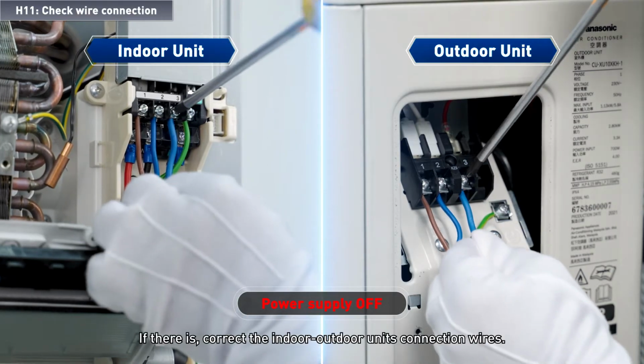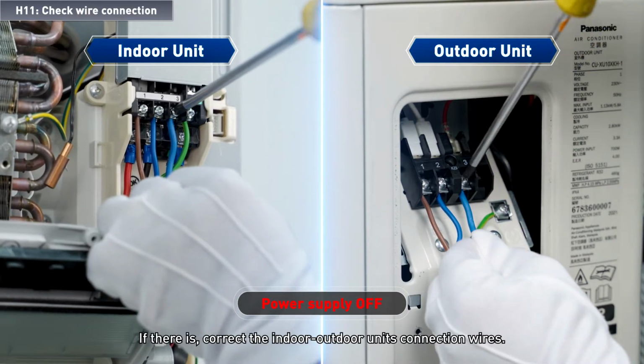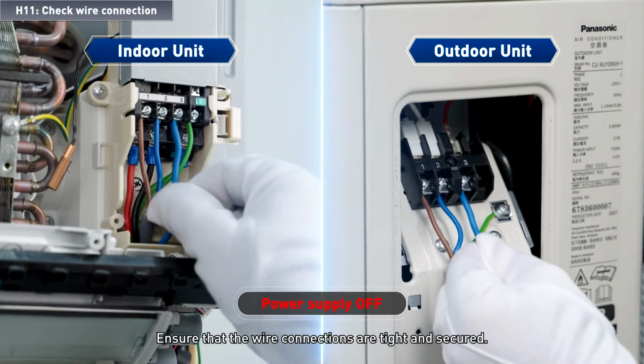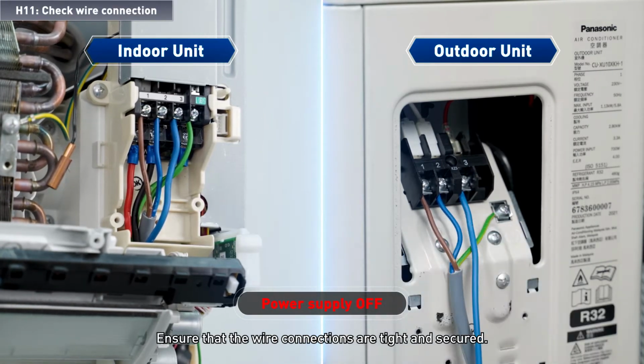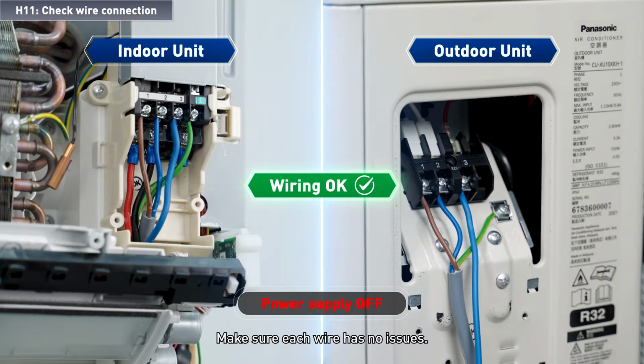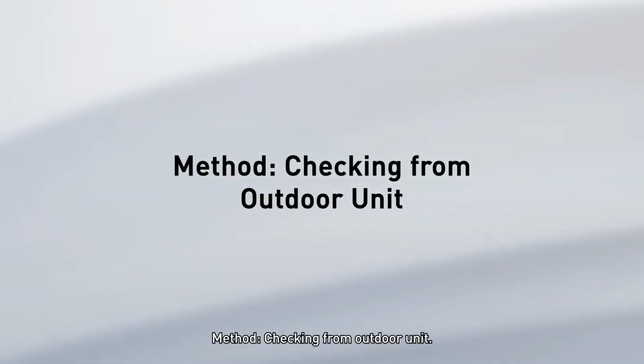If there is, correct the indoor-outdoor unit's connection wires. Ensure that the wire connections are tight and secured. Make sure each wire has no issues. Method: checking from outdoor unit.